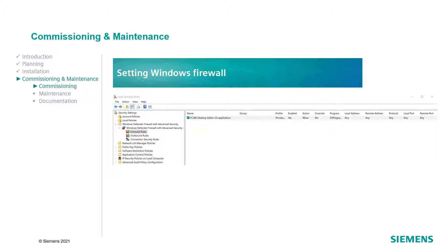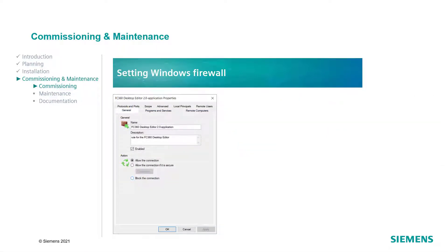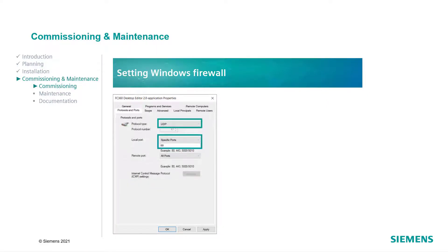There are some additional settings which need to be done. To make sure that the rule is appropriately set, right-click on the rule and select Properties. Go to the General tab and verify that the Enable checkbox for General and the Allow the connection checkbox for Action have both been selected. In the Protocol and Ports tab, select UDP for the protocol type, specific ports for the local port with the value 69, and all ports for the remote port. Confirm the selections to enable the new firewall inbound rule and connect the panel and the PC.